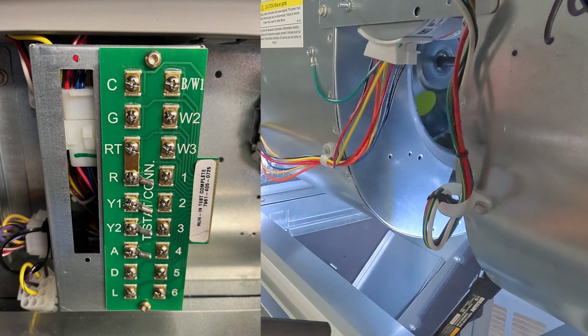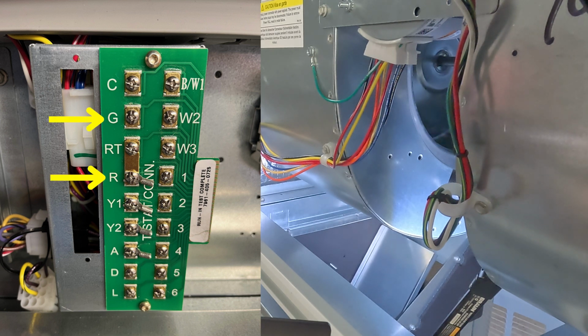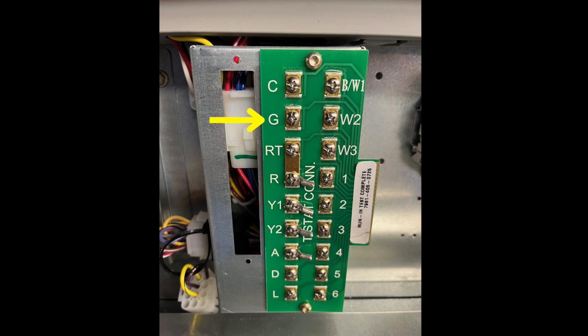To have the indoor blower motor energize with the CRV, jumper R to G and A. Energizing G and A with 24 volts will open the damper and run the indoor blower. This allows an independent ventilation operation separate from comfort conditioning. This basic non-CO2 sensor control method has two choices. Do you have a stat or EMS with a separate function to control ventilation independent of heating or cooling? If so, then energize terminal G and A on the low voltage terminal block.